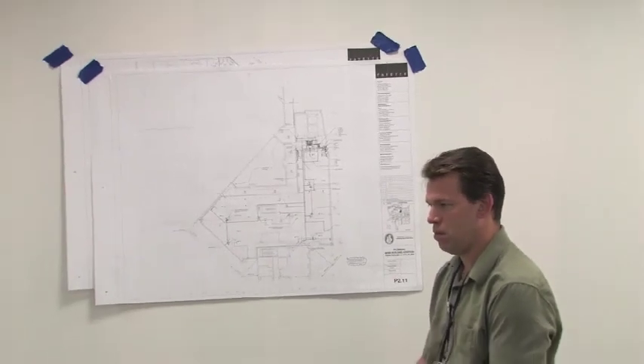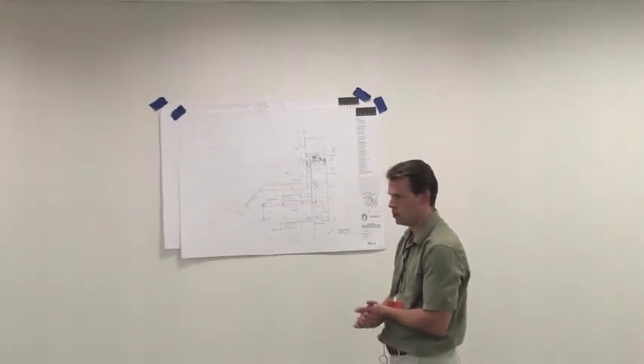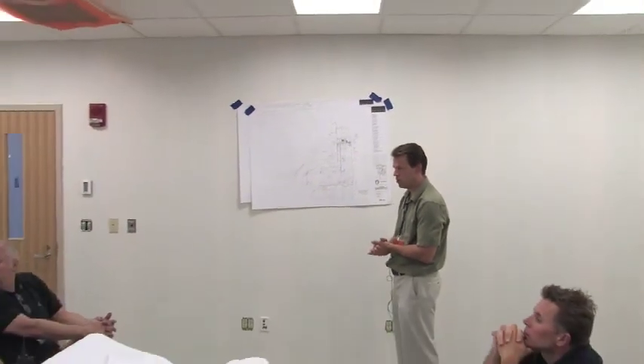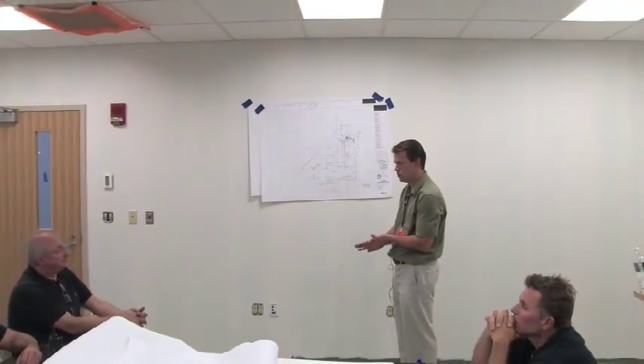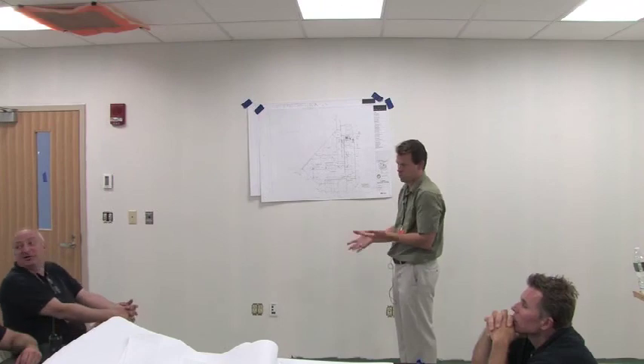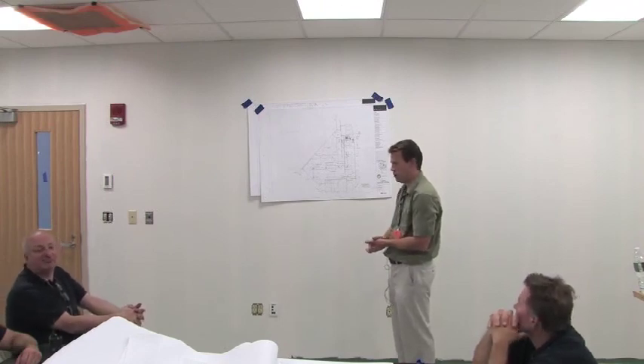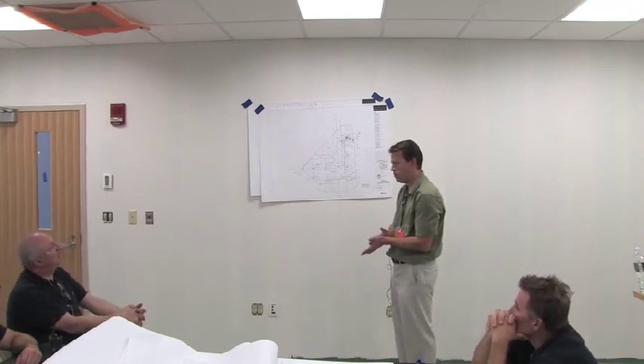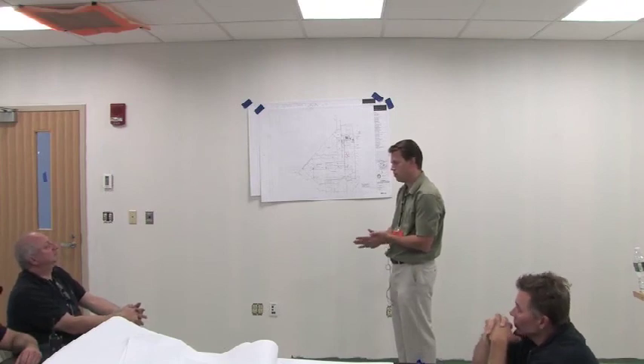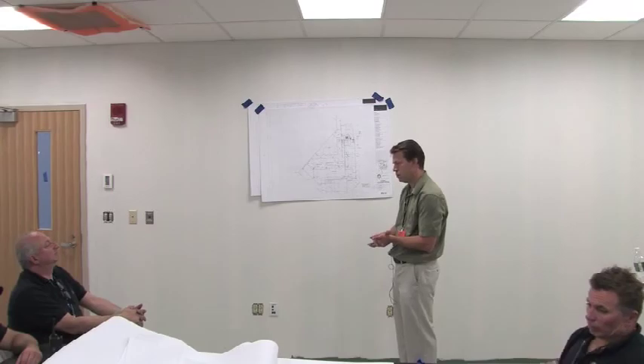In the off-season, you could shut it down. I'm just thinking out loud, but part of our procedure is, if the cooling tower's not running and the chiller's not running, we shut the pump off, shut it down, and drain it if you want. I'm almost to the point where I might enable the run command on that pump: when the tower runs, it's able to run; if not, it isn't enabled to run.